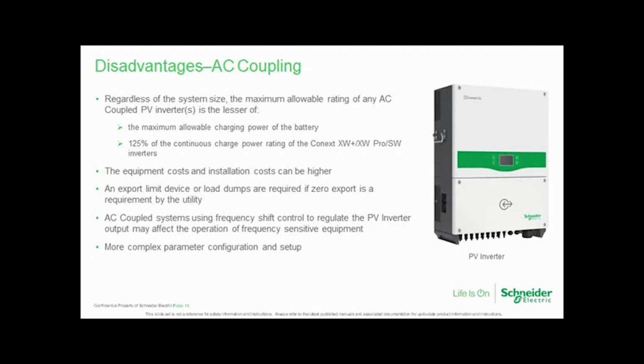Now, we come to the disadvantage of AC coupling. Basically, regardless of the system size, the maximum allowable rating of any AC coupled PV inverter is the lesser of the maximum allowable charge power of the battery, or 125% of the continuous charge power rating of the Conext XW Plus, XW Pro or SW inverters, which means, for example, if you have a 6.8 kilowatt XW Plus, the maximum PV inverter you can hook up to it would be 8.5 kilowatts.